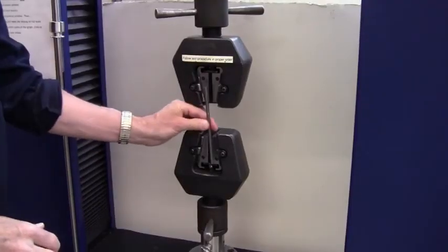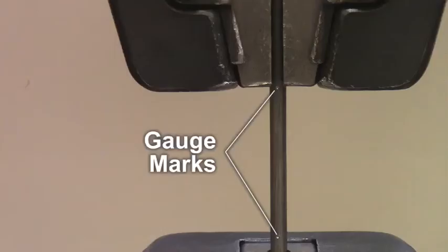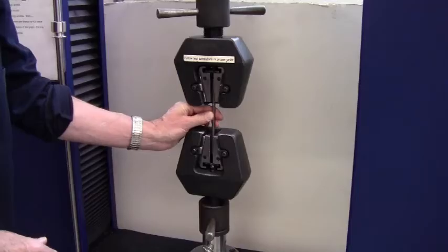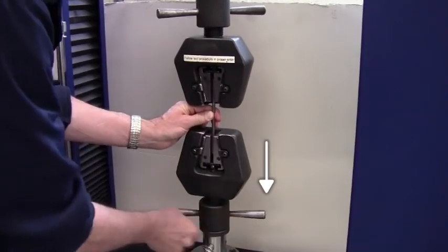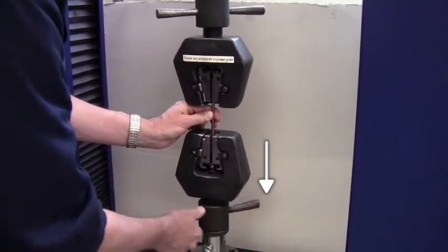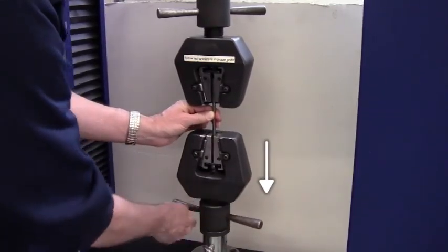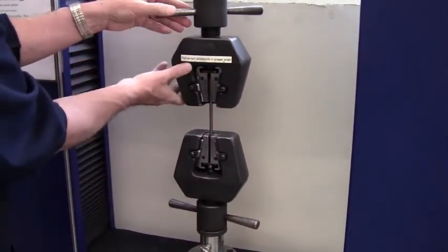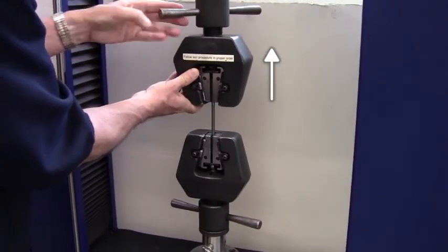Time to put the sample in the grips. When mounting, make sure the gauge marks are between the jaws. Starting with the bottom, move the grip downward to tighten it on the steel rod. Do the same with the upper grip, but raise it to tighten.